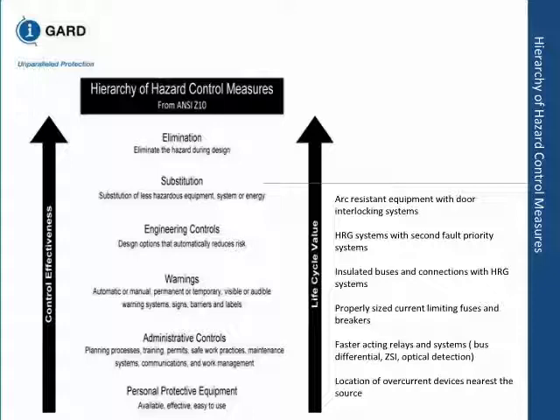You decide which one is going to be taken off. Okay? You use insulated buses in combination with a high-resistance grounding system. Even though it may not be considered part of elimination, at 90 to 95% it can be considered elimination. Phase-to-phase fault will be protected by the insulated bus, phase-to-ground will be protected by the high-resistance grounding system. Use properly sized current limiting fuses and breakers so they can operate in the current limiting range. Don't size the biggest fuse to protect the transformer. Take care of arc flash first.